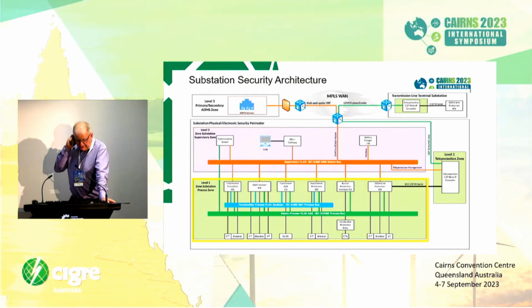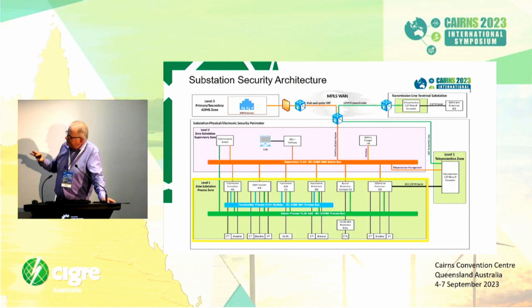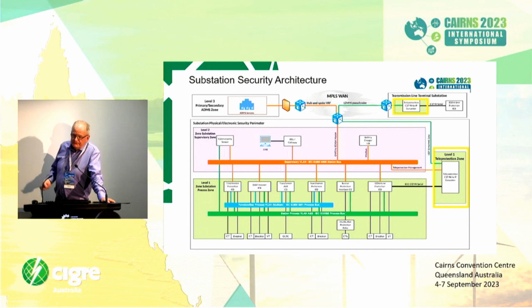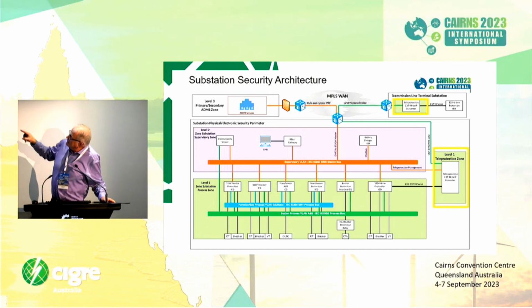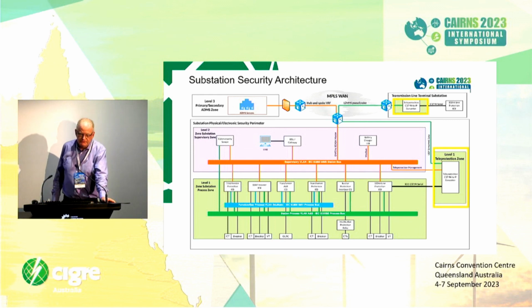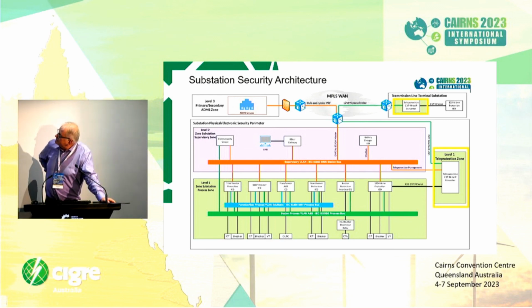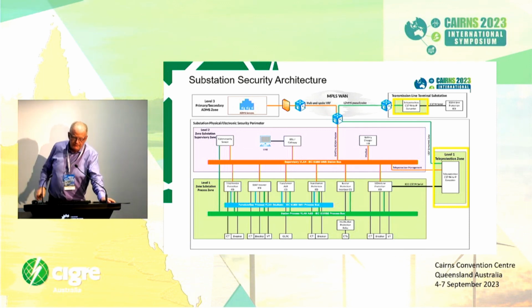Then we've also defined a process zone that's aligned to IEC 61850 process buses, if you like, that just contains all the GOOSE traffic and 61850 sampled value traffic on separate VLANs within the substation. Then we've got our teleprotection zone itself, completely separate, that has a connection back through the MPLS network, using a layer 2 pseudo wire connection, back to the terminal substation at the other end. Importantly, that's all kept segregated from the other parts of the network.